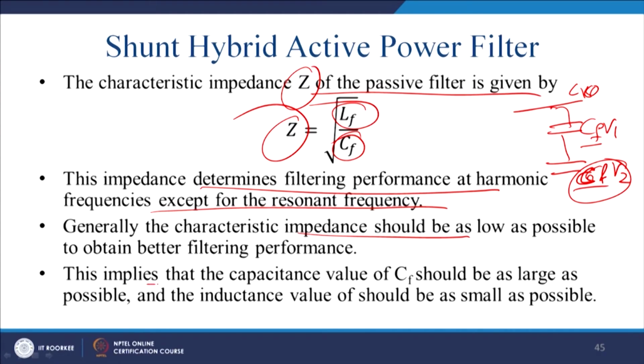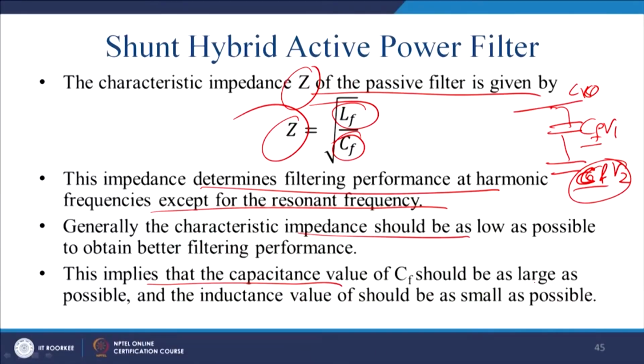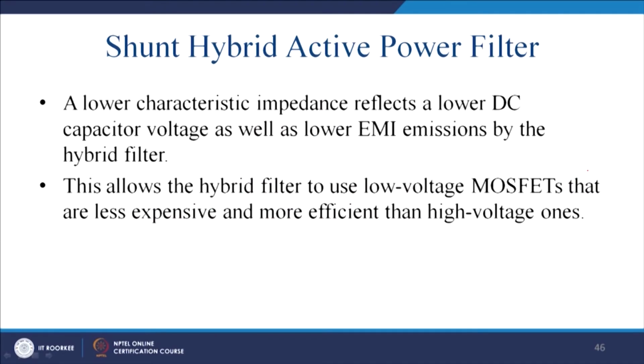This implies that the capacitance value CF should be as large as possible and the inductance value should be as small as possible, so that your surge impedance becomes lower. But it is in direct conflict with the rating of the device. The rating of the device will come down if the value of CDC is more and CF is less.